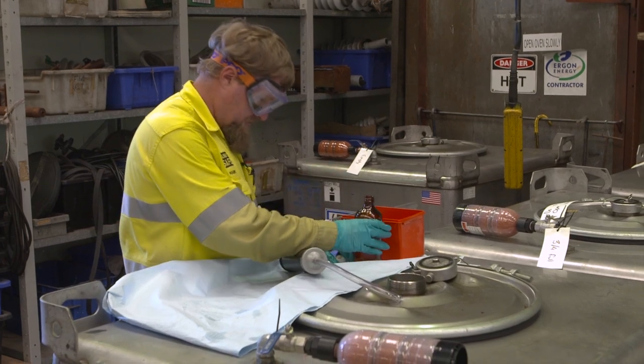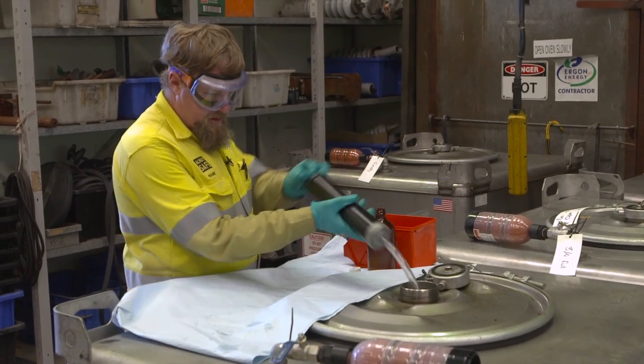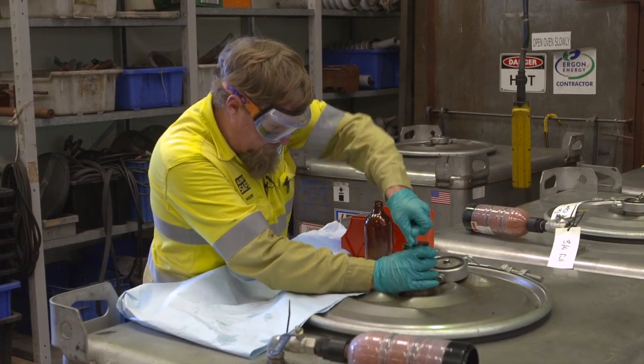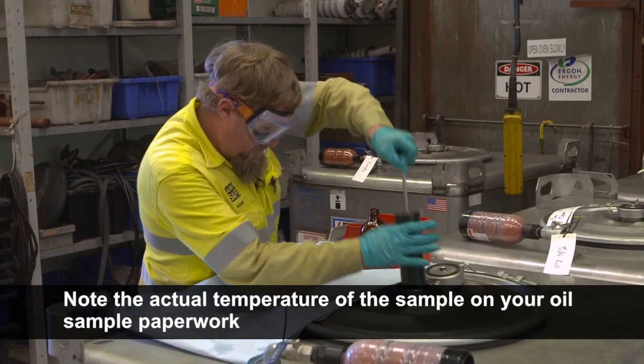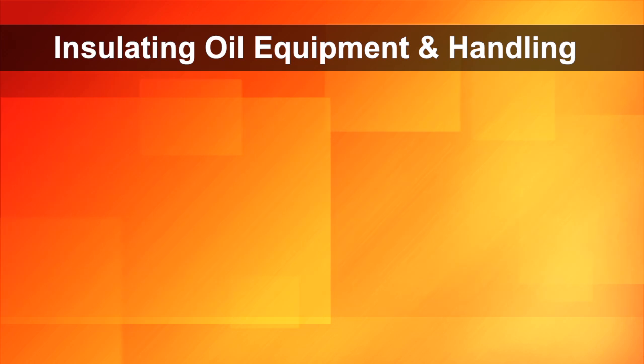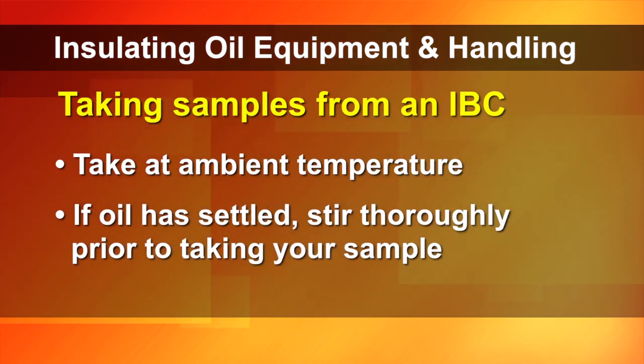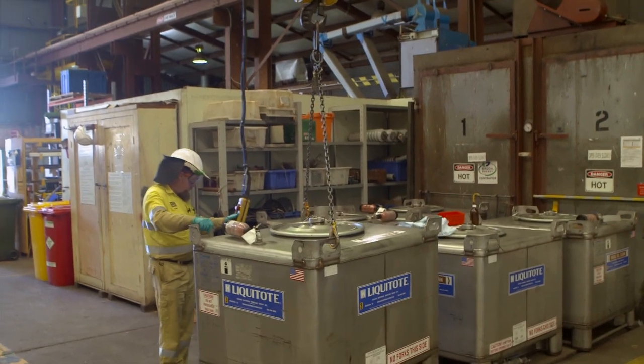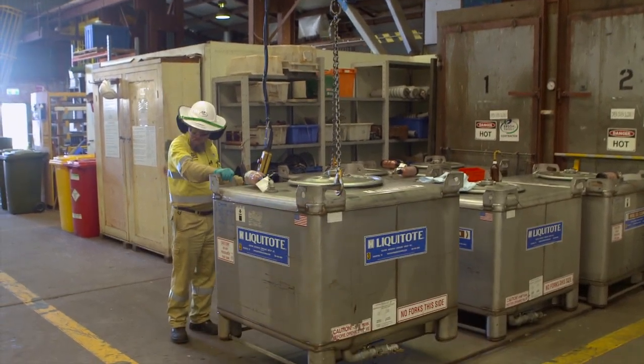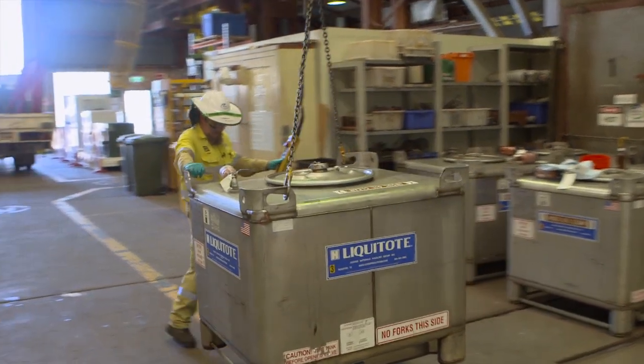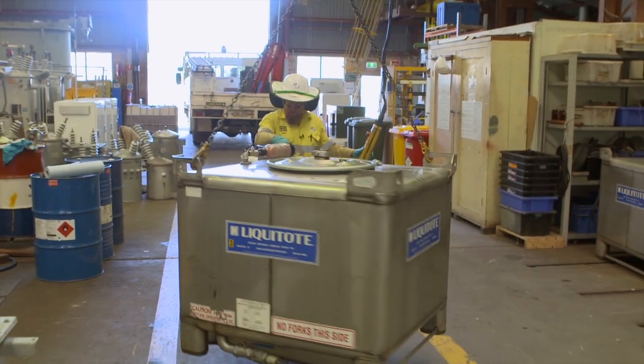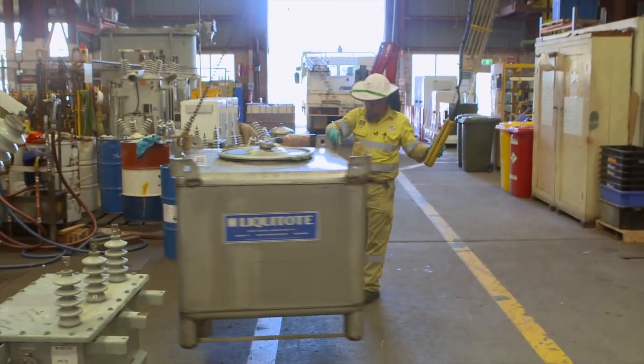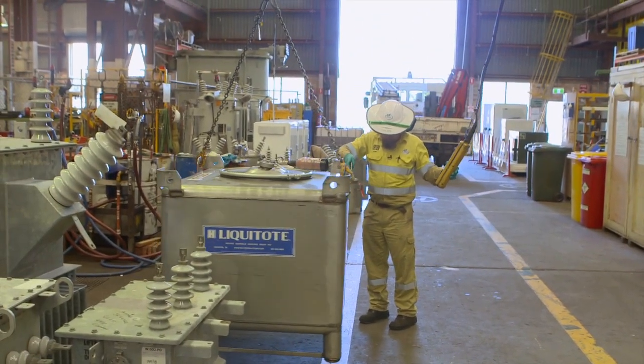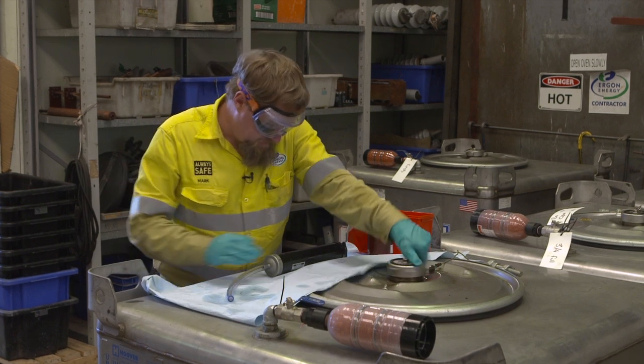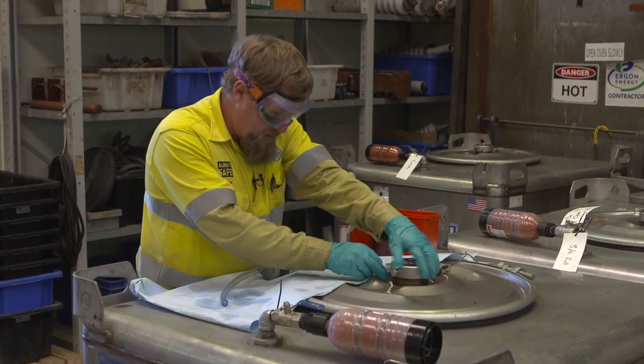A couple of things that are important about taking samples from IBCs to remember are, firstly, the sample should be taken at ambient temperature. It's also important that if your oil has settled for some period of time, it is stirred thoroughly prior to taking your sample, because experience has shown us that oil will actually settle into pockets of different dielectric or breakdown voltage strength over time. So by stirring the oil, we'll get a more accurate value for the average strength of the oil in that IBC. I'll now do a sample. Just remove the lid.